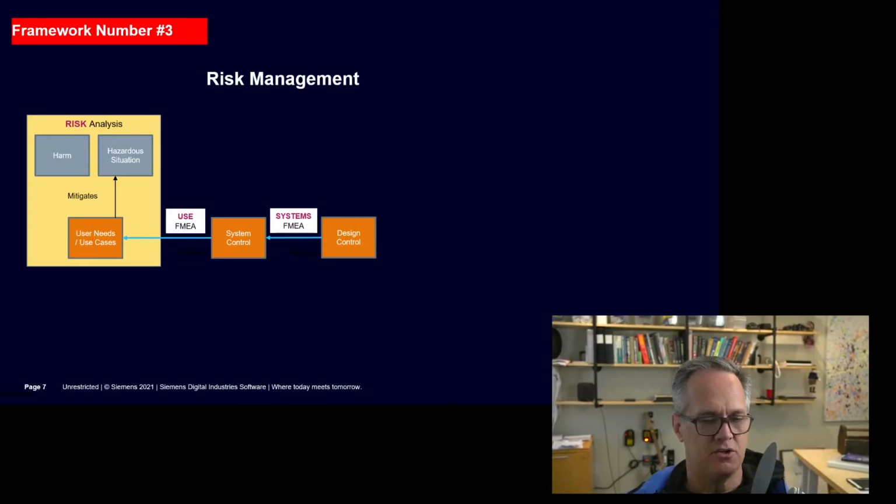Now, that design control would probably be pulled in from a standard. So what we would do is we'd say, we have a system control that is compliance with the 11135 standard, but in our library, because we're doing this kind of sterilization process all the time for this product type, we would have a 11135 compliance standard document with all the requirements and test cases that we need to be able to do the verification and validation of this particular problem.